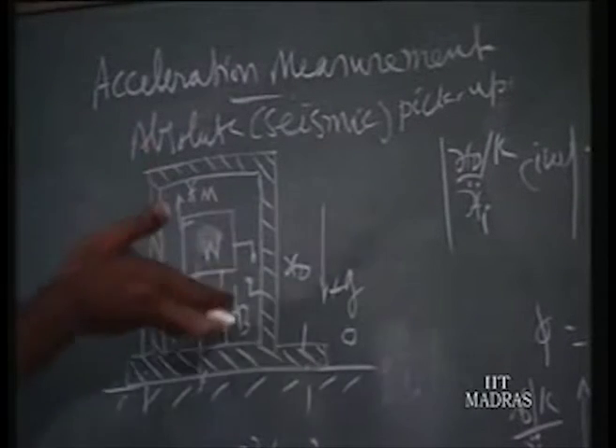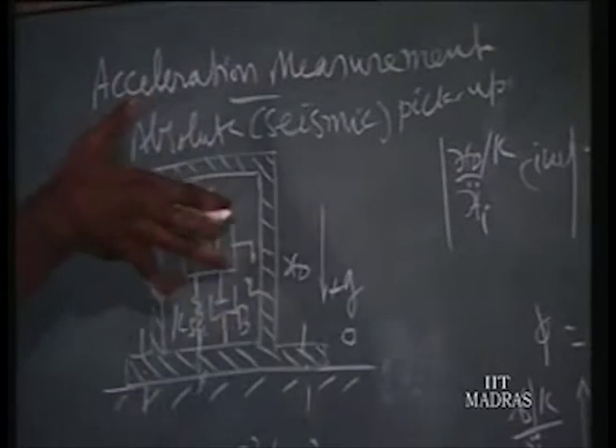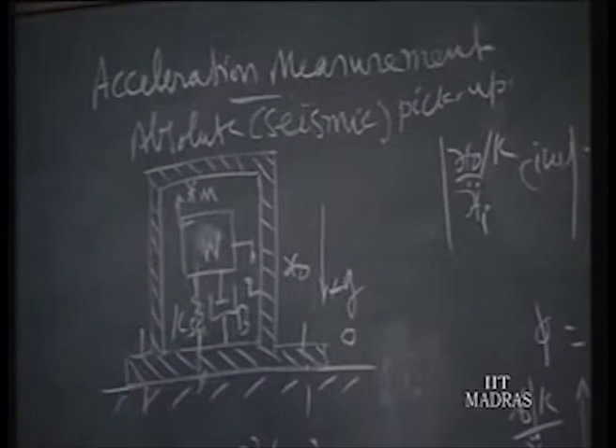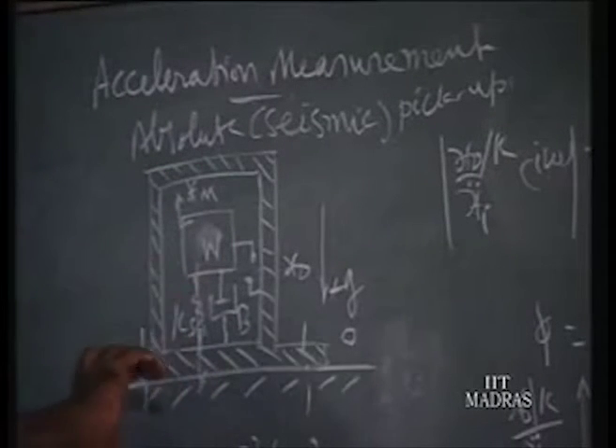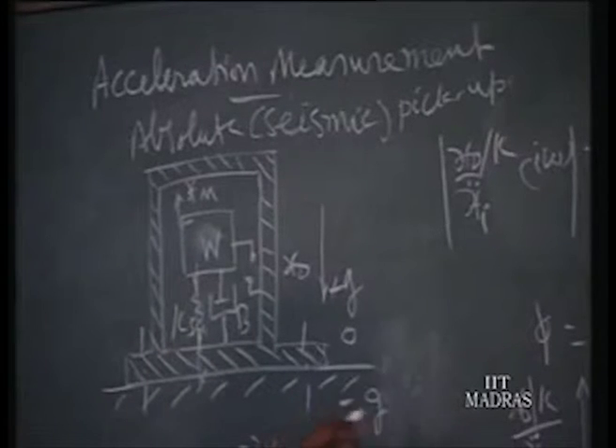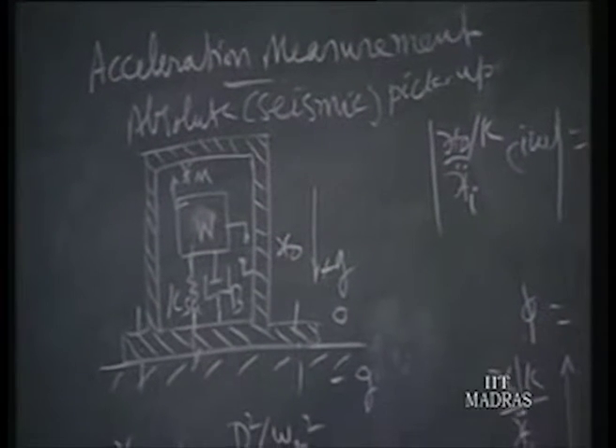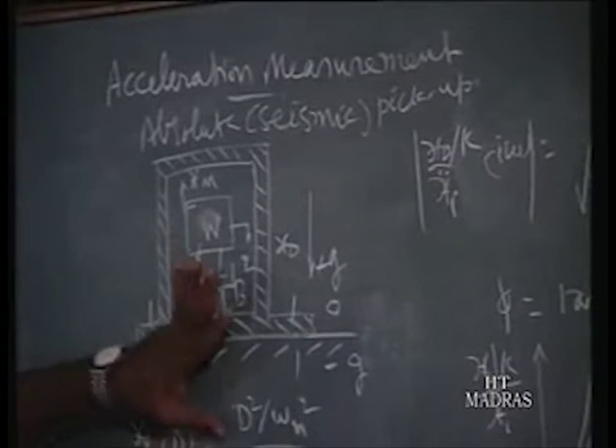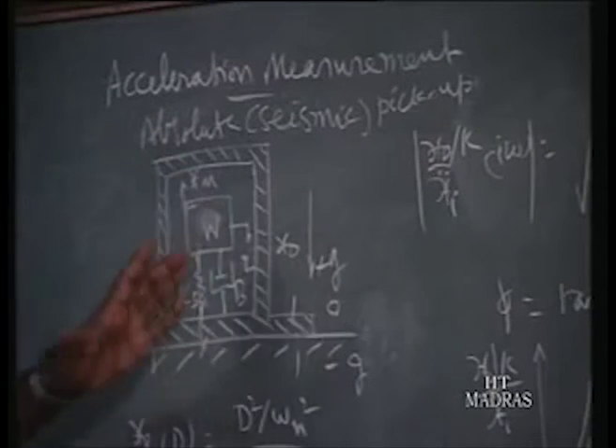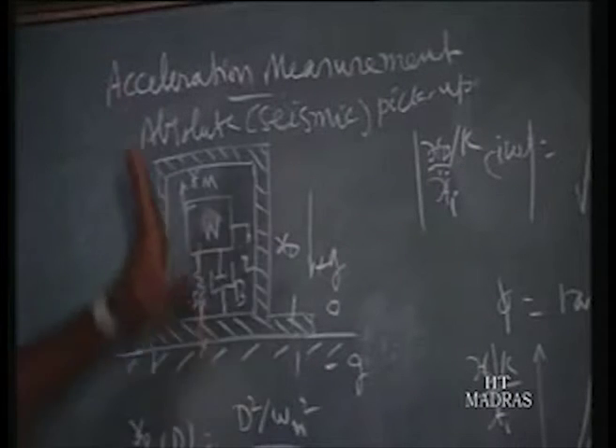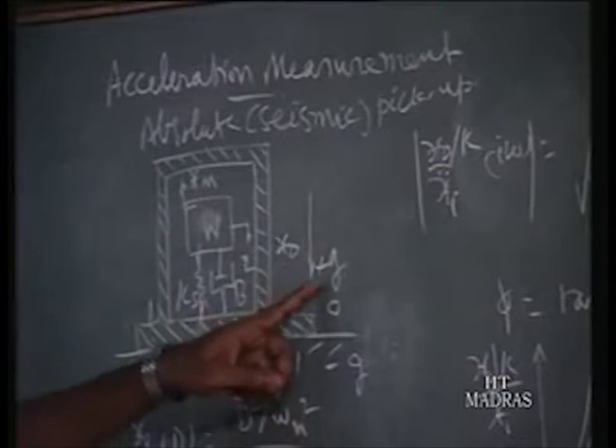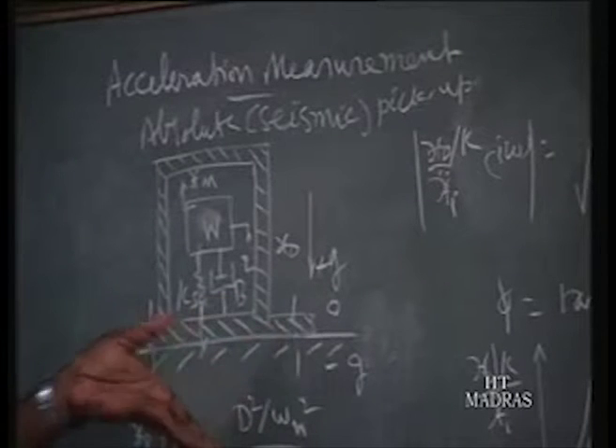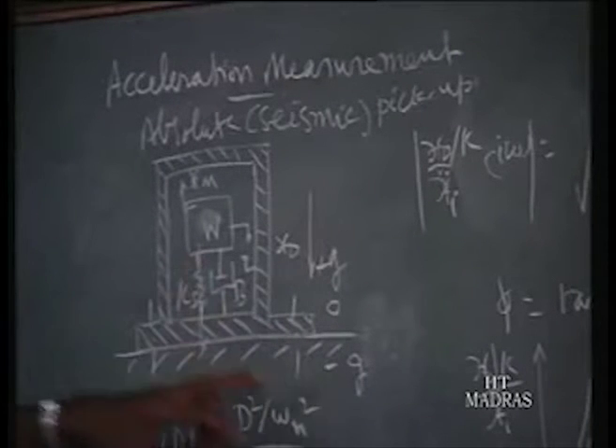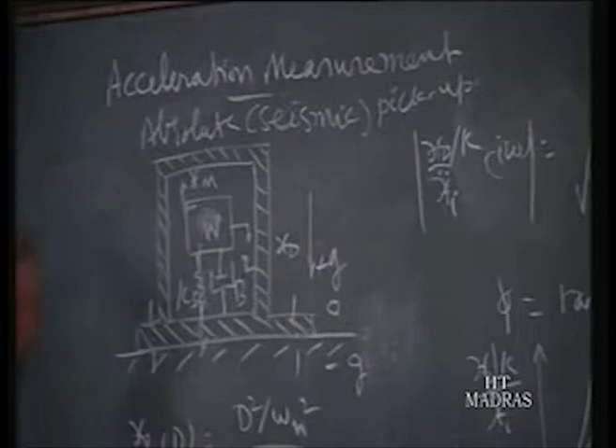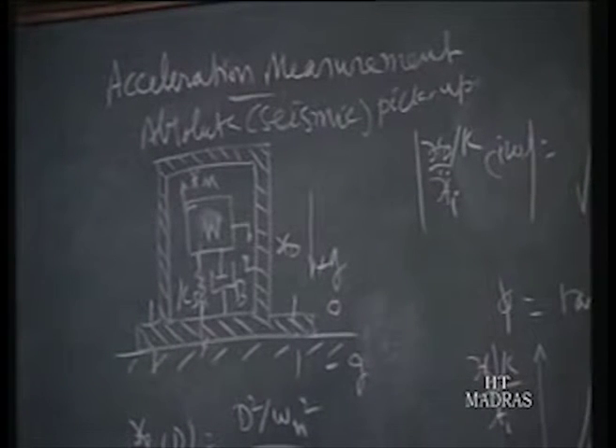Now tilt another 90 degrees, so it will be fixed upside down. This will be top and this will be bottom. That means G will be acting in the opposite direction, and you will have minus G. That is how the three readings are obtained in an accelerometer. You can check any accelerometer by mounting it in these three ways. First, with G along the measurement direction, you will get plus G, then tilt 90 degrees, 0, another 90 degrees upside down, that means minus G. So you can measure on both sides, plus G and minus G, in both directions.